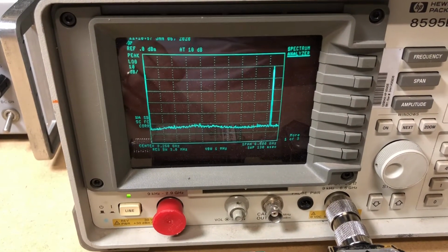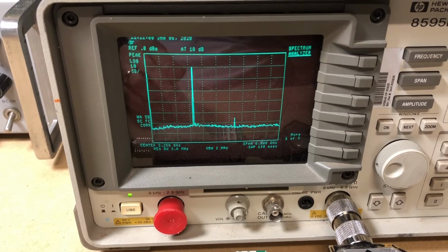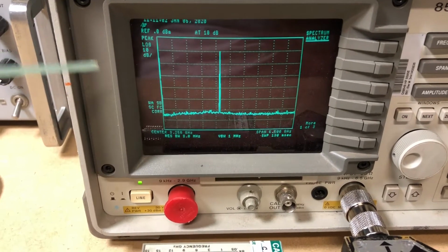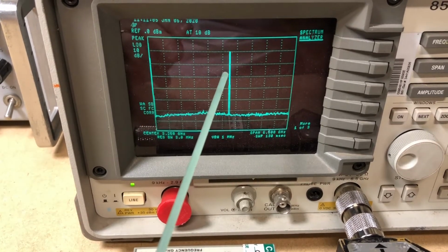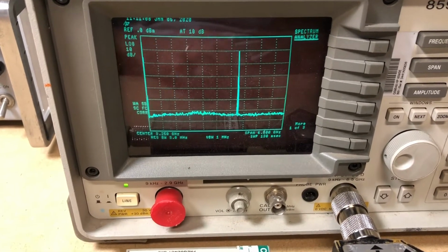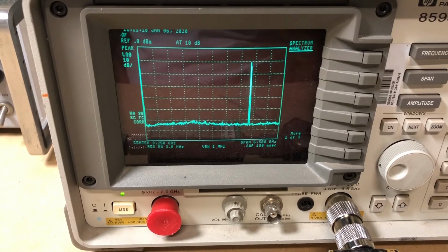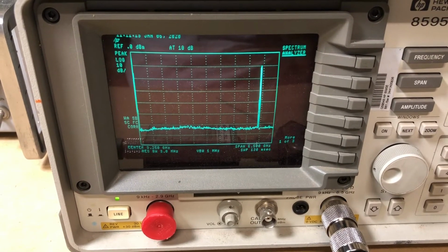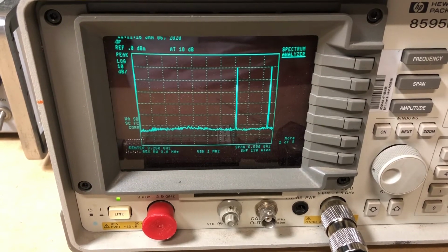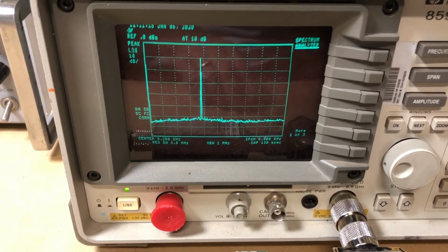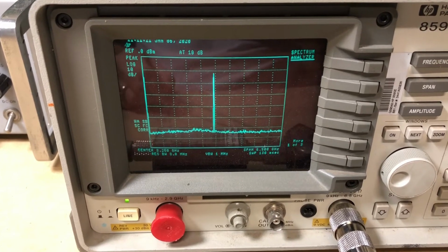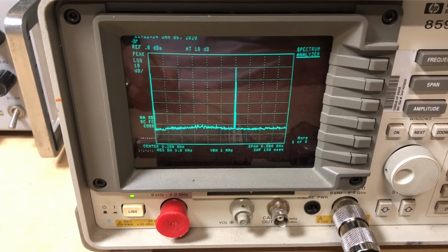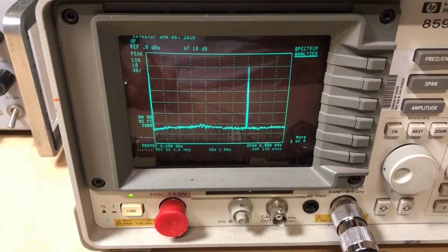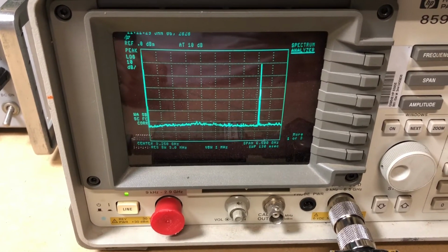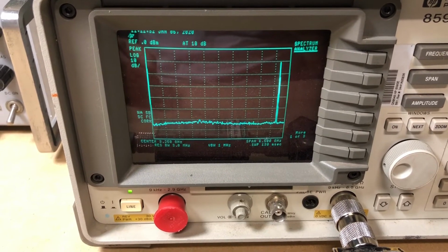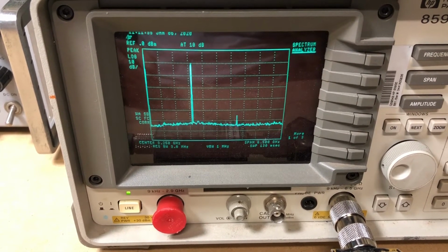So it looks like our problem has been resolved, because here's our tone, as we can see, and it's sweeping all the way across the full band. And we're not getting those losses, that drop off in power, like we had before. So it would appear that simply running the cal YTF routine fixed the problem. I don't think the cal frequency or the cal amplitude really fixed it. I think it was probably running the cal YTF.